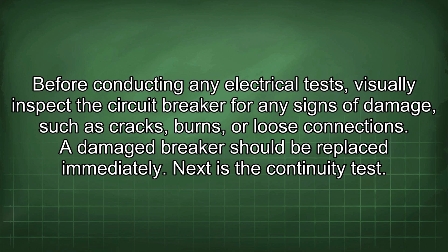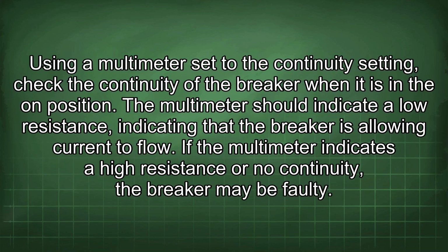Next is the continuity test. Using a multimeter set to the continuity setting, check the continuity of the breaker when it is in the on position. The multimeter should indicate a low resistance, indicating that the breaker is allowing current to flow. If the multimeter indicates a high resistance or no continuity, the breaker may be faulty.